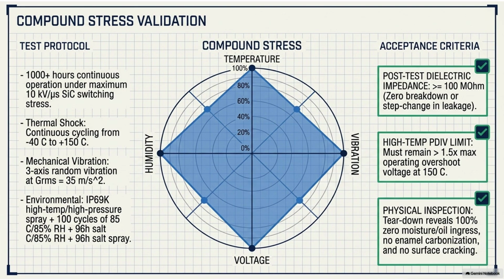Now, standard factory testing usually involves a high pot test, basically blasting it with high voltage to see if it immediately shorts out. Yeah. But a high pot test is too blunt to catch a micro scratch, right? Yeah, a standard high pot test is completely blind to early stage degradation. That's why advanced lines use 100% online partial discharge testing. They inject a highly calibrated 2.5 kilovolt surge, specifically designed to catch weak discharges that standard tests miss. We are talking about detecting discharges at the scale of less than 10 picocoulombs. Right. A picocoulomb is 1/1,000,000,000,000th of a coulomb of electrical charge. It is almost imperceptible. If even a single microscopic manufacturing defect made it past the needle winding and the VPI process, the surge test will illuminate that 10 picocoulomb leak and the unit is scrapped.